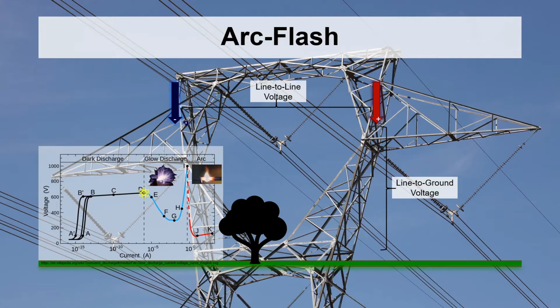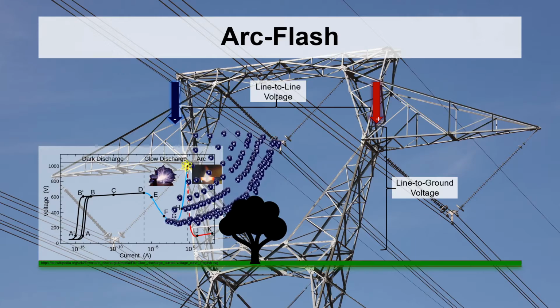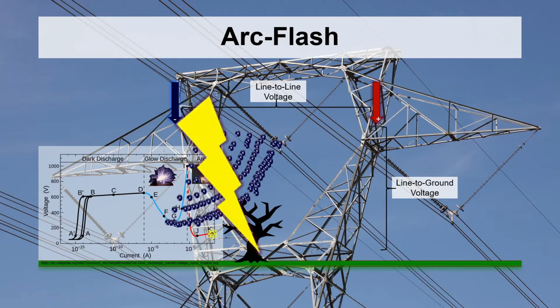So to illustrate: one electron runs into more, an avalanche effect happens, leaders start forming, and those leaders form until they complete the circuit in a plasma trail—and boom, you get an arc flash event. The current goes up to whatever is limiting it in terms of power, and the energy source dumps all of its energy at that point.